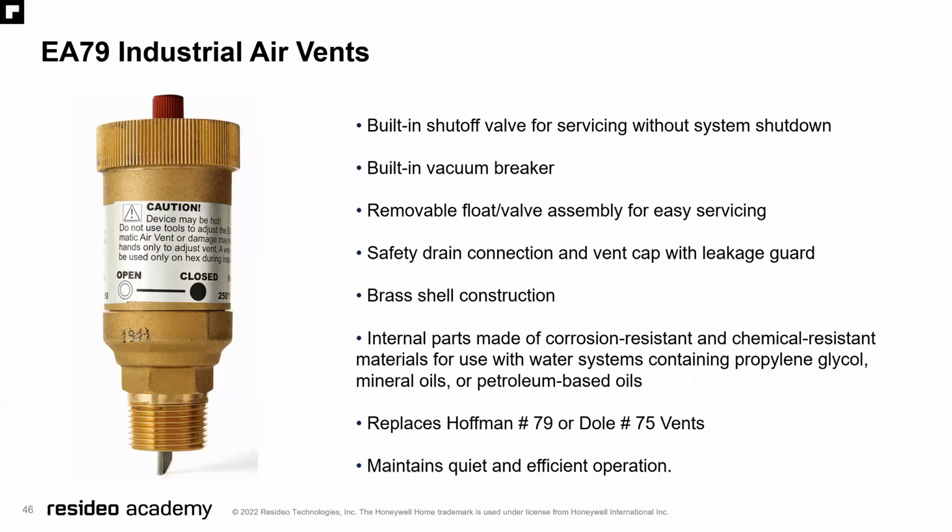Has a built-in vacuum breaker. The float valve and assembly is removable to allow easy servicing. Safety drain connection and vent cap with leakage guard, brass shell construction. The internal parts are made of corrosion resistant and chemical resistant materials for use with water systems containing glycol, mineral oils, or petroleum-based oils. Replaces the Hoffman number 79 or Dole number 75 vent. Maintains quiet and efficient operation.